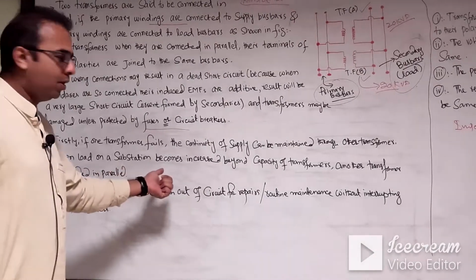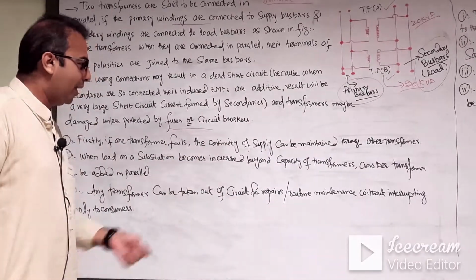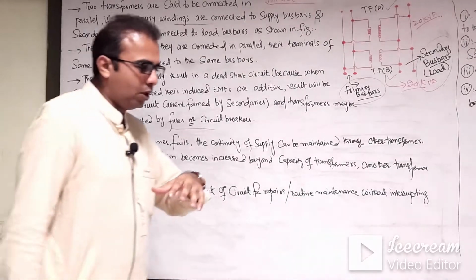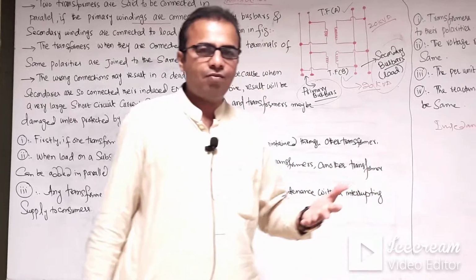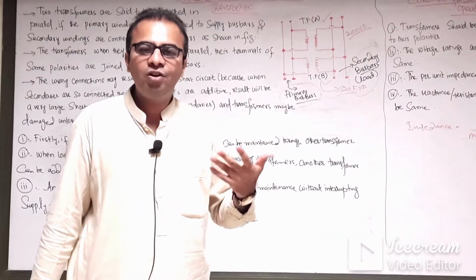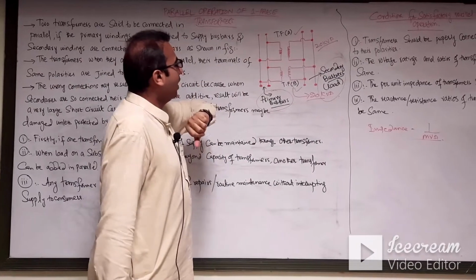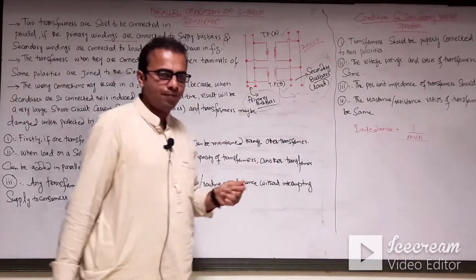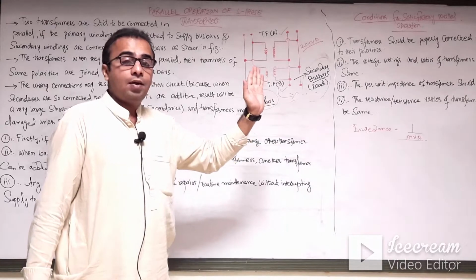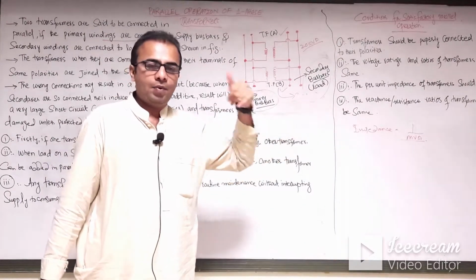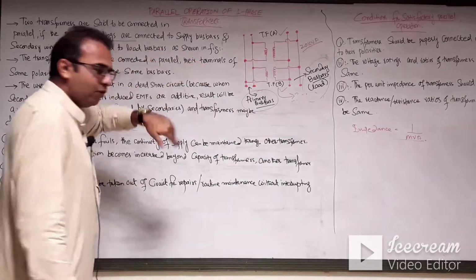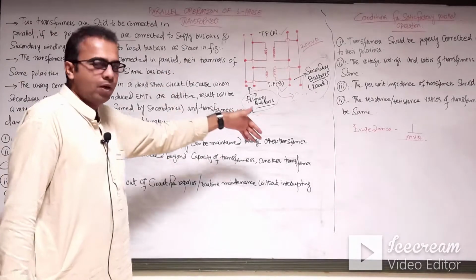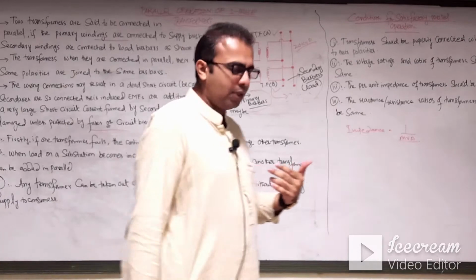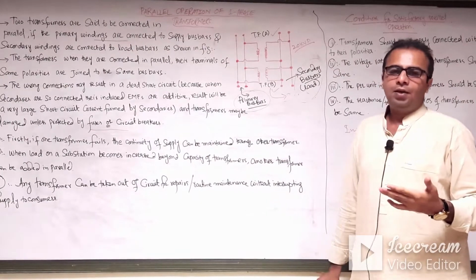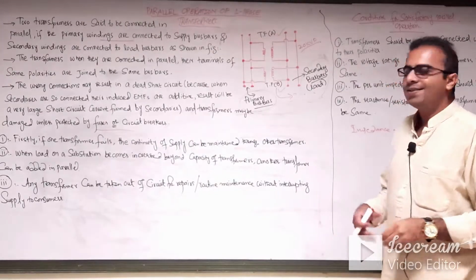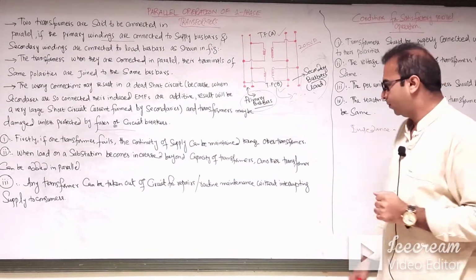Second, when the load on the substation increases beyond the capacity of the transformer, another transformer can be added in parallel. If the load is increased beyond the capacity of any electrical machine, it may cause harmful effects. For example, if transformer A has an apparent power rating of 20 kVA and the load is increased beyond its capacity, we have to share the load or put the load on transformer B, to maintain the continuity of operation and also reduce the burden on transformer A. So this is also an advantage of the parallel operation of the transformer.